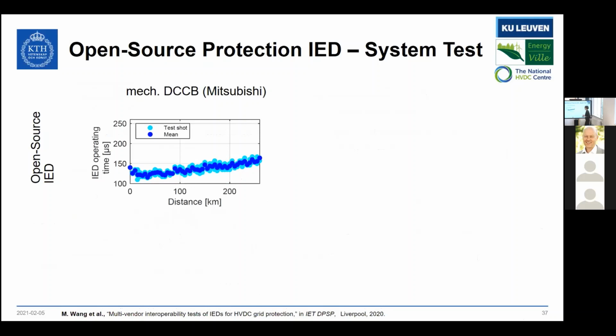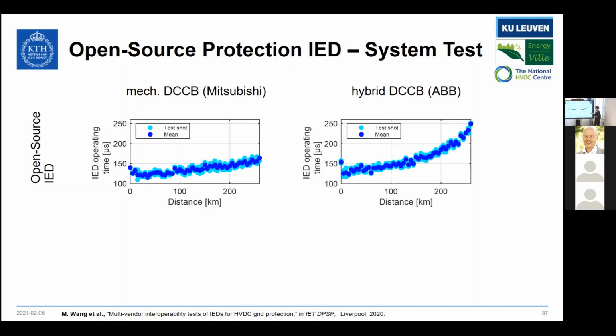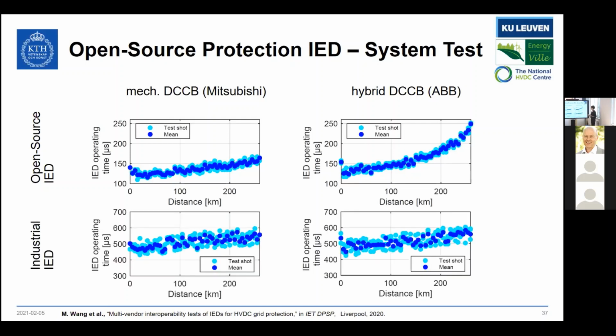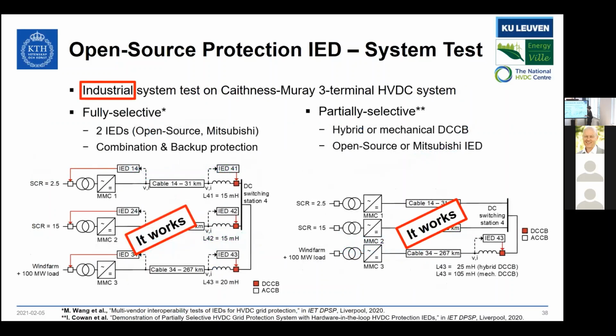And it's the same behavior as before. We see on the x-axis a distance. This is a combination of the open source IED with the mechanical DCCB from Mitsubishi. And on the y-axis, you see the IED operating time, which is similar to the values we've seen before. And it looks almost the same also for a different DCCB and for the other IED. So to keep it short, again, several combinations work. So several combinations of IEDs and DCCBs fulfill the functionality to achieve the protection performance we want.